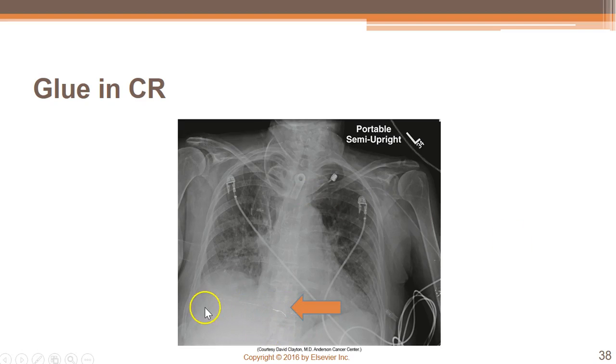So it's this line. But even that line, most radiologists would know that that's not in the patient, but you may have to take something out just to make sure. So with that, the residual glue on it resulted in an artifact, and they actually had to take that plate out of service so that it wasn't used again because it couldn't be cleaned.